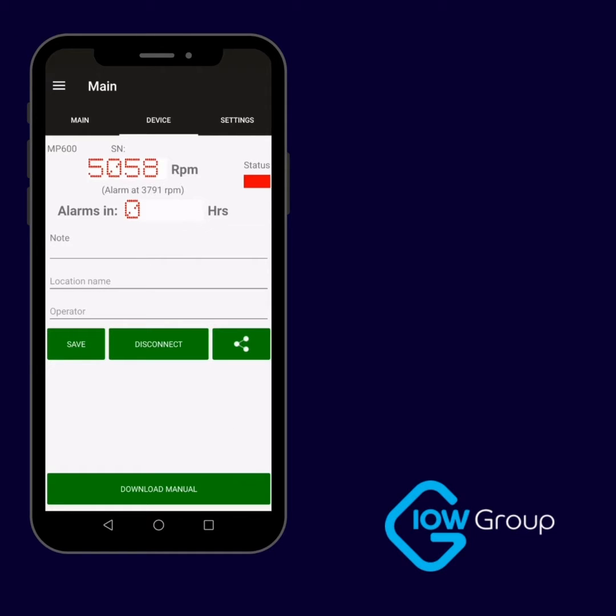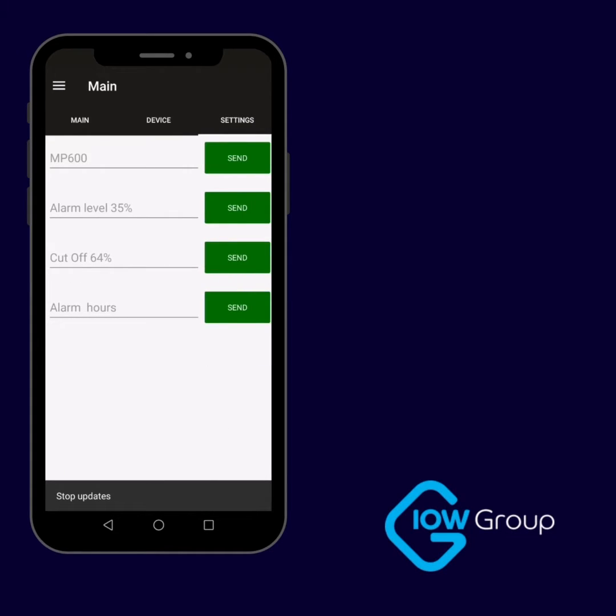If you go across to your Settings tab, this is where you can change your device's alarms. Today we're going to set up an alarm so the centrifuge is serviced after 350 run hours, which we enter here.